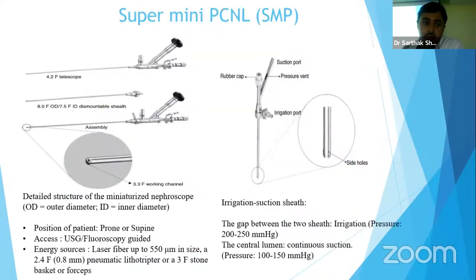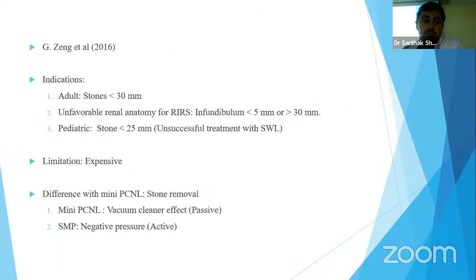Super mini PCNL uses a 4.2 French telescope with an 8 French outer diameter, 7.5 French inner diameter sheath. After assembly, you can see there is a 3.3 French working channel. There is a special irrigation suction sheath where the gap between the two sheaths is for irrigation, and the central lumen is for continuous suction of 100 to 150 millimeters of mercury.